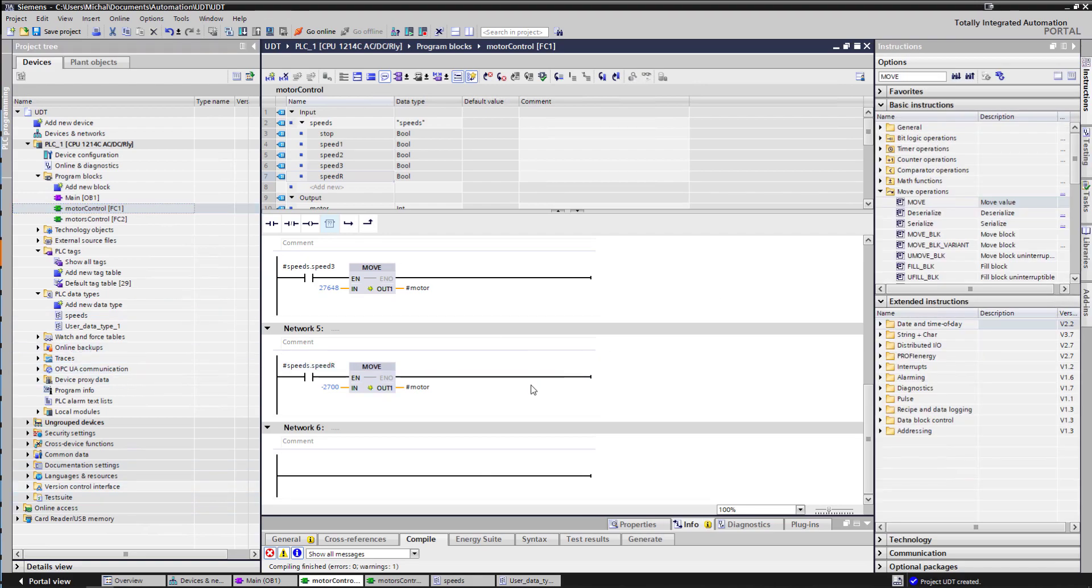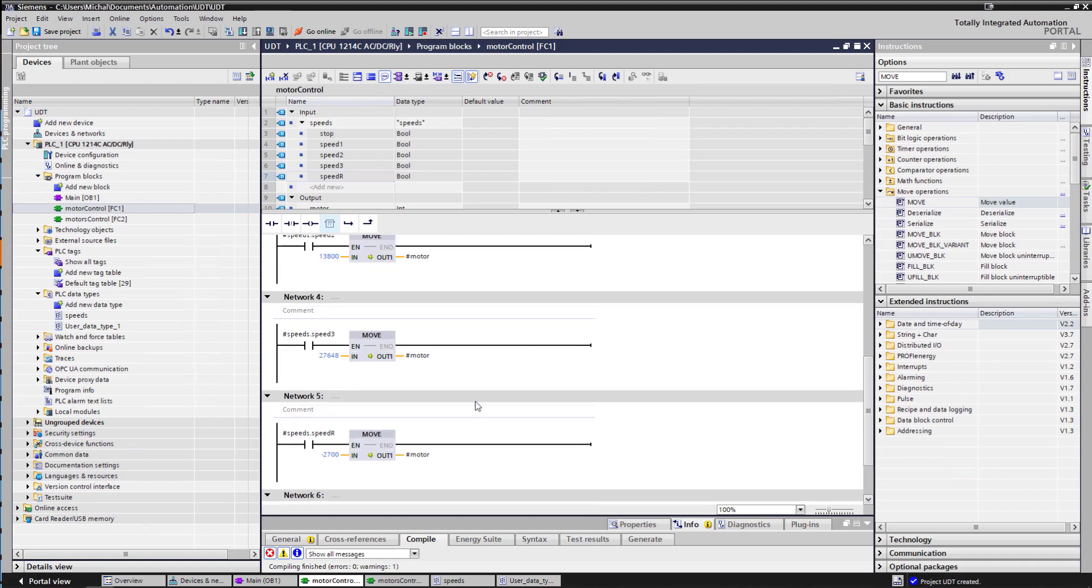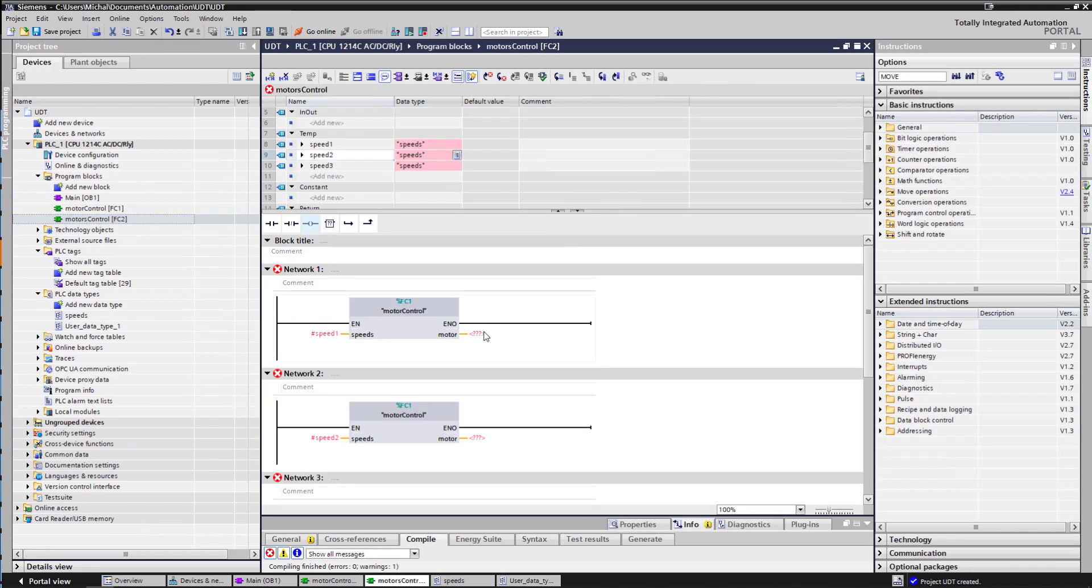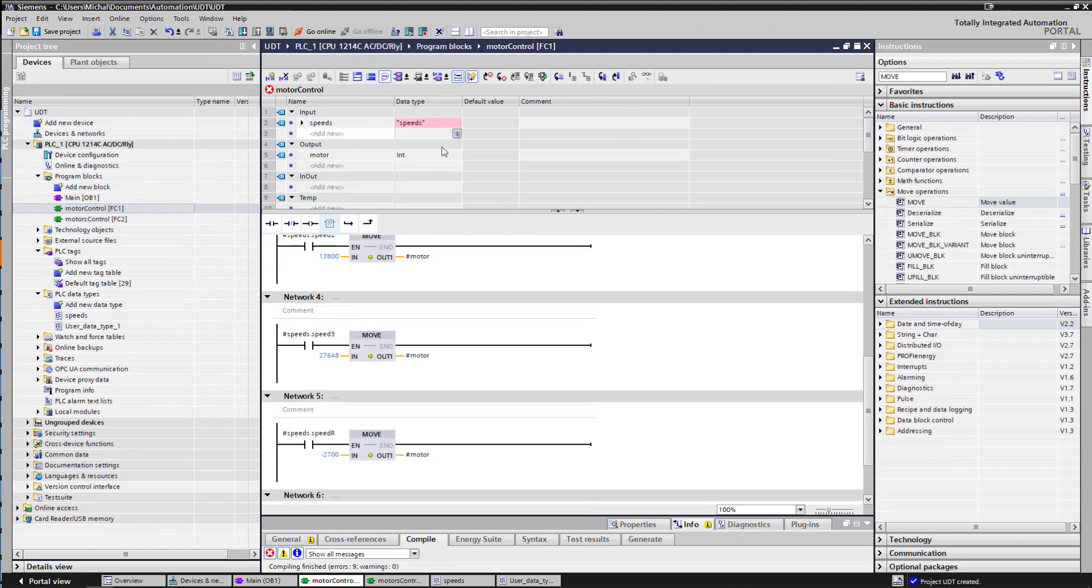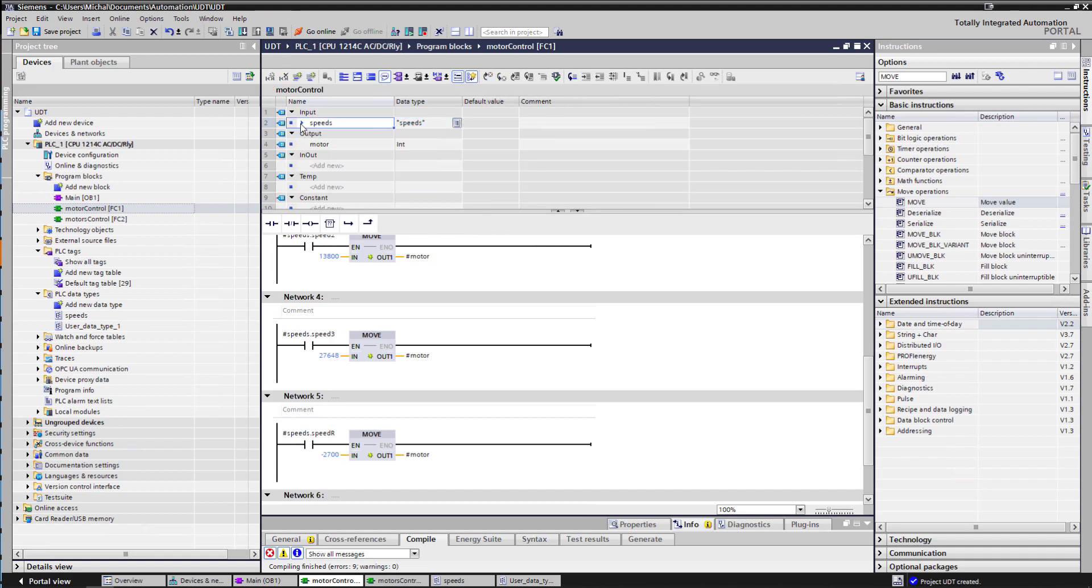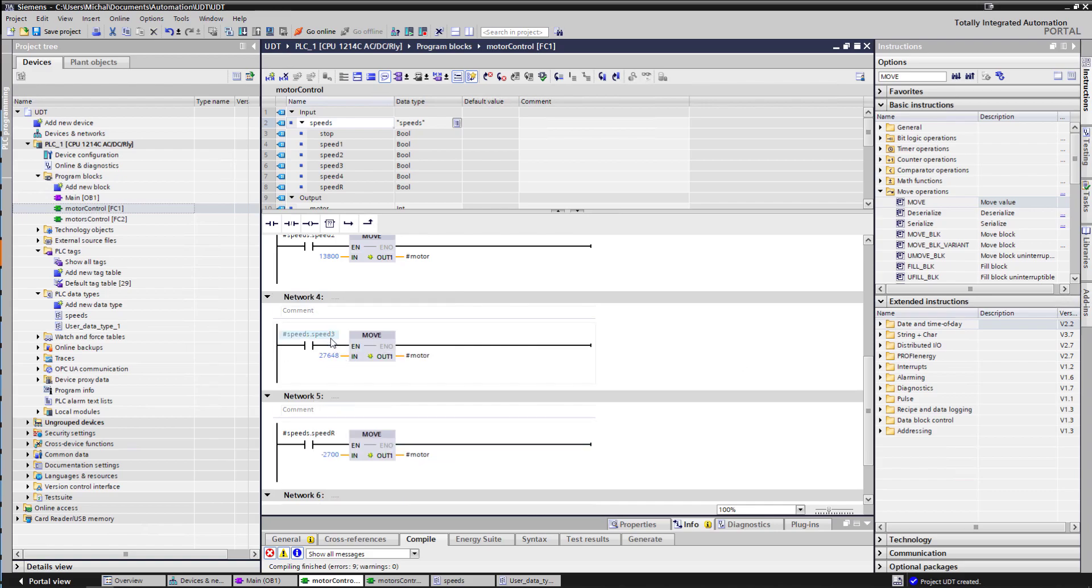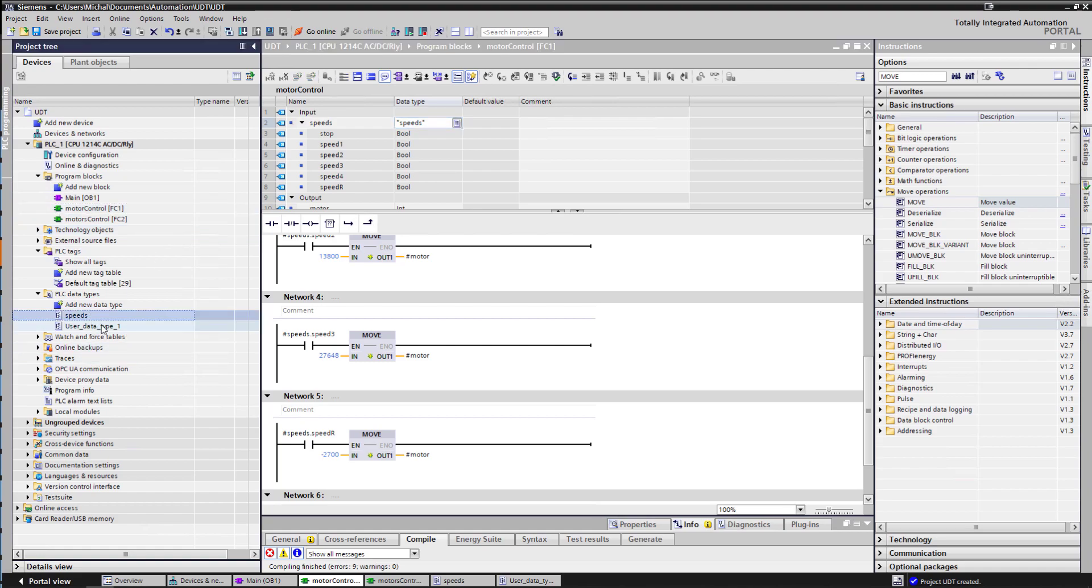But all this is to help you manage things in one place. Because if I now want to change, I change my idea, and I no longer have only three speeds, maybe I now have four speeds. I would only go here, add myself a new row, and say speed 4. Yeah, so this makes it much, much easier. I would, of course, need to readjust. I would need to readjust my function. So my motor control function would now have four speeds. But I'm only handling three speeds. So if I wanted to do it, again, I would insert a new network and handle speed 4 to be something different. But it means that I only have single places that I need to worry about, rather than now having to go into struct in every single block that I have, and modifying it manually. So I make a change here in speed and it is propagated throughout my code.